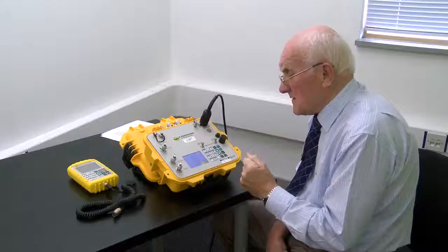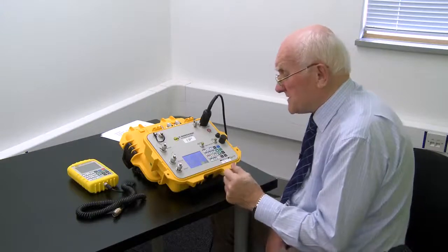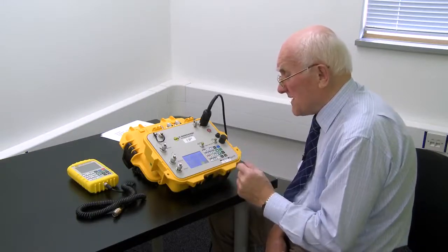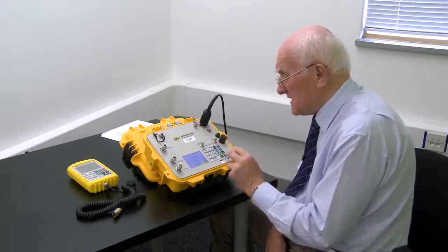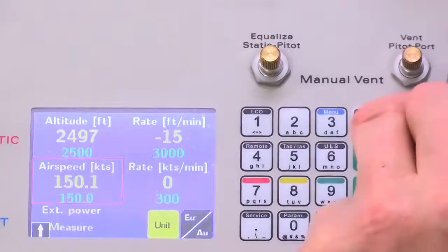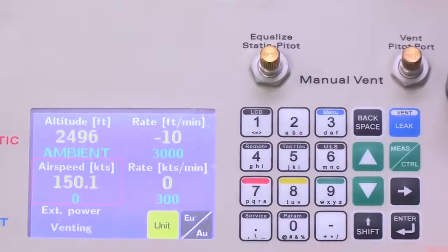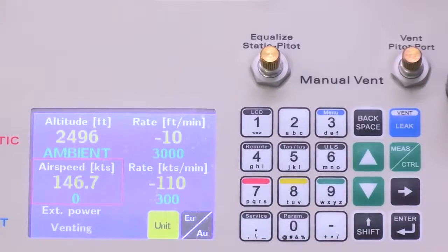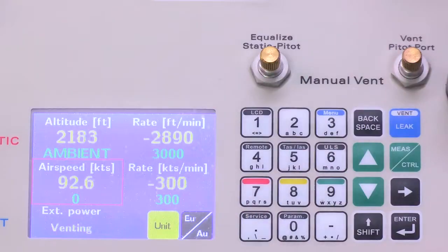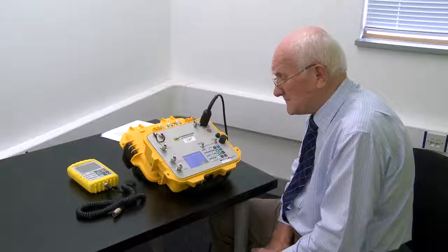That's good, so it's closed. Now perhaps we're at the end of the test and we can take it down safely to ground level using the venting key. So we press shift and vent, and go. It's taking us now to the ambient pressure, just as it did when we started, bringing us down so everything is stable at ground level.